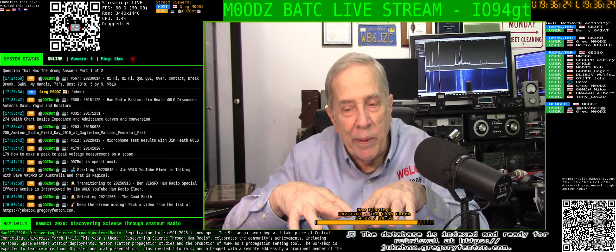It's best to run each one, I use a pipe we talked about earlier, instead of daisy chaining them. If you daisy chain them, this one may be 10 ohms, this one 8, this one 6, this one 4. Instead, run them all to that ground rod, and then that goes to your grounding system.